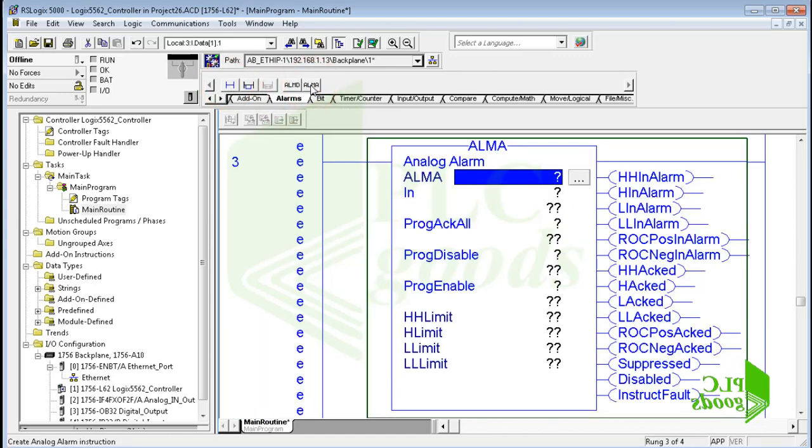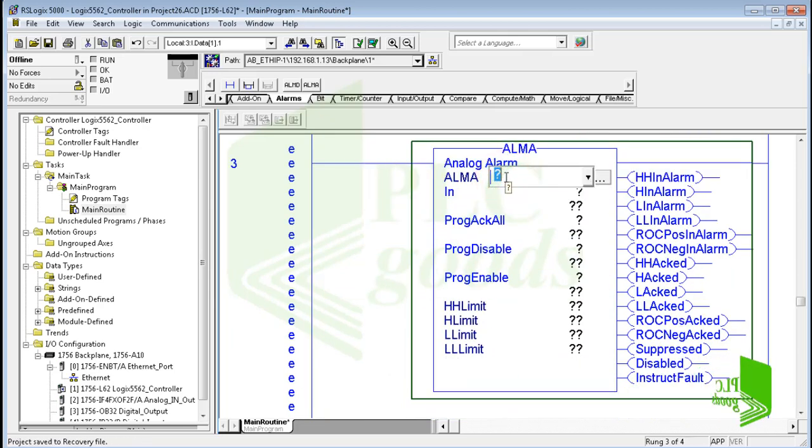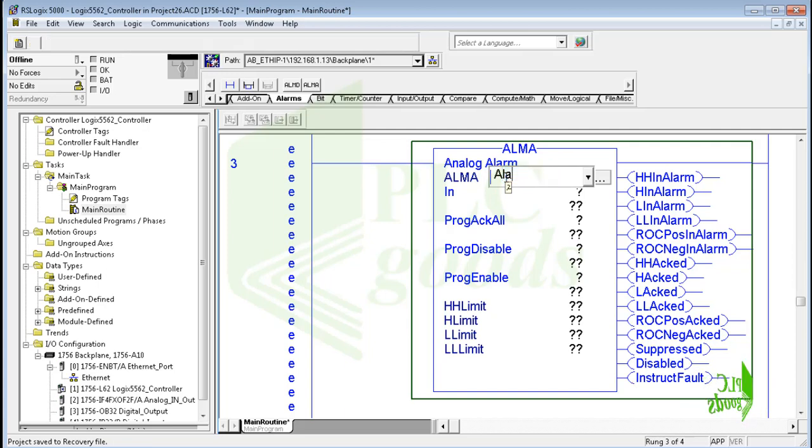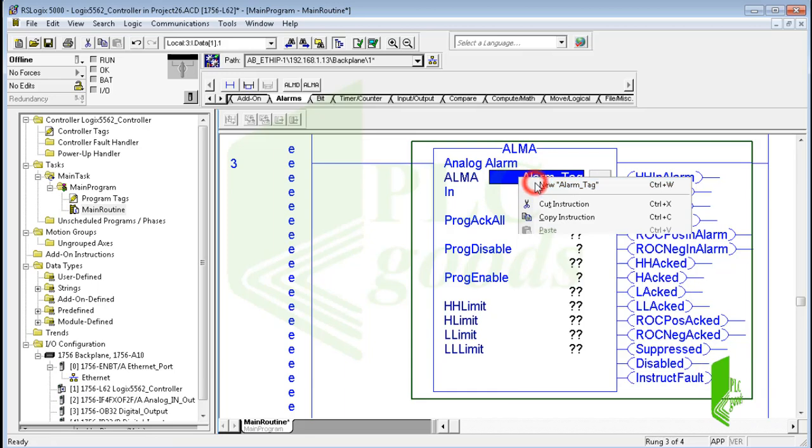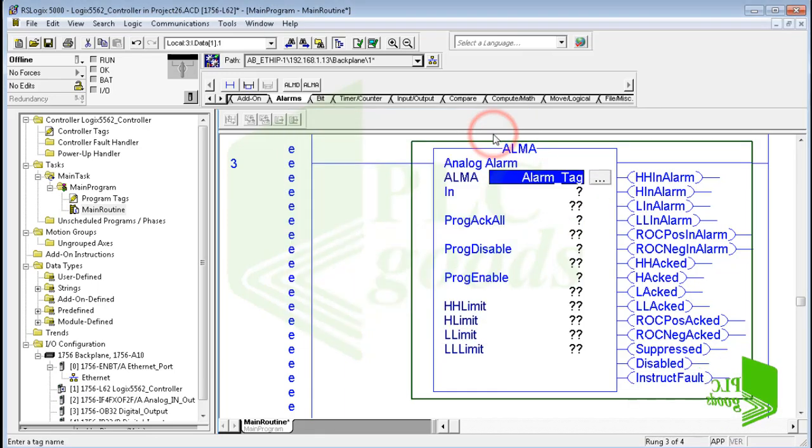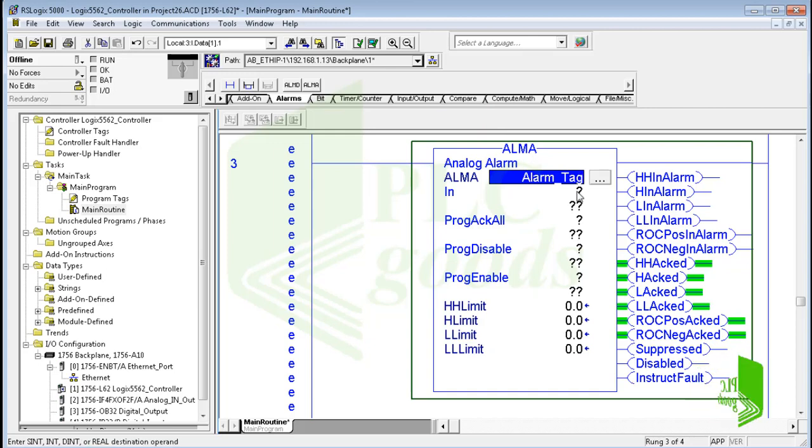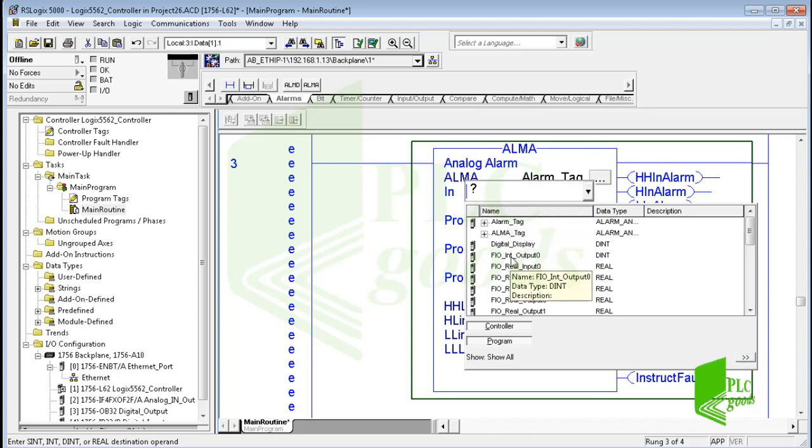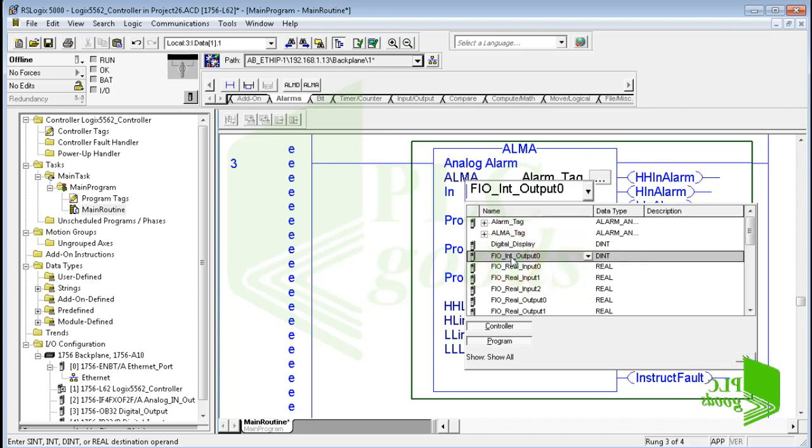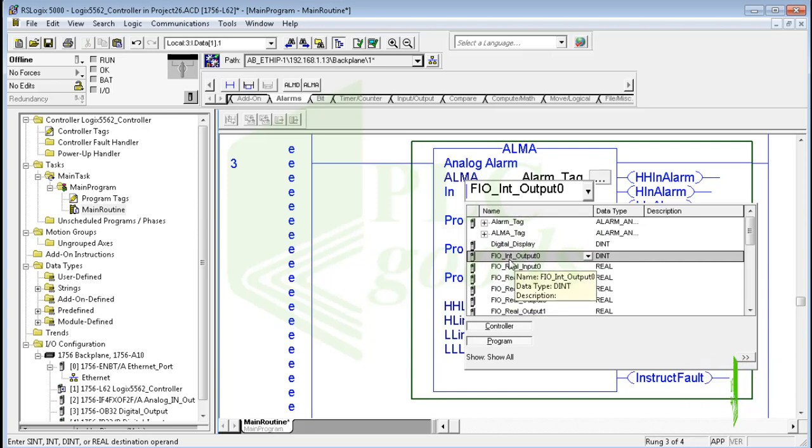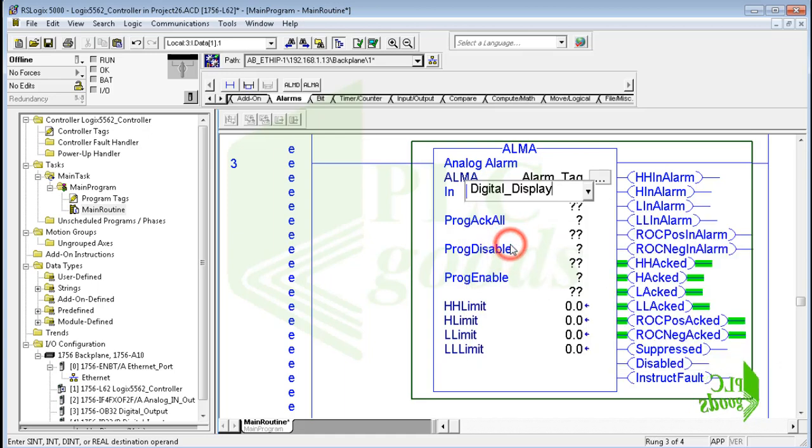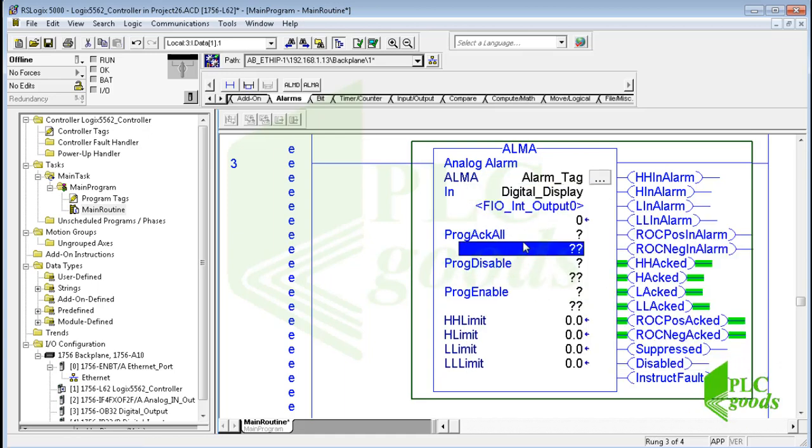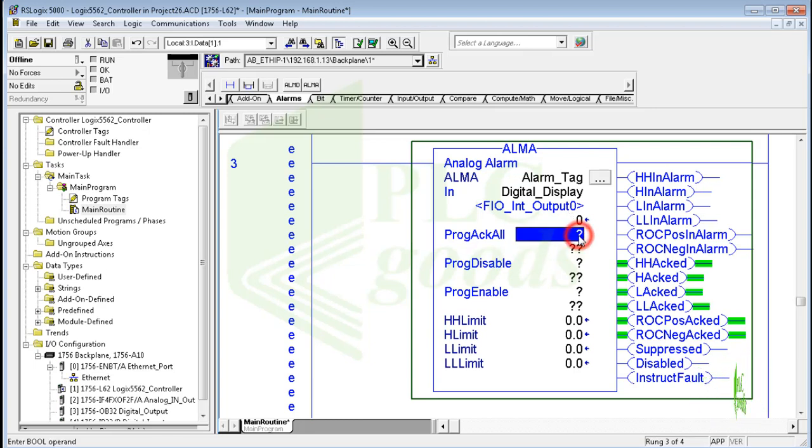As you see, it has many parameters. All of them will be created under a name tag. So at the first step, I must define a tag for the inserted analog alarm instruction. Note that the new tag data type is ALARM_ANALOG. Then the alarm input value must be determined. Its value will be compared with alarm limits to detect the alarm condition. I can select this tag, FIO_Int_Output0, which represents the water level, or select this alias type tag which is connected to FIO_Int_Output0.